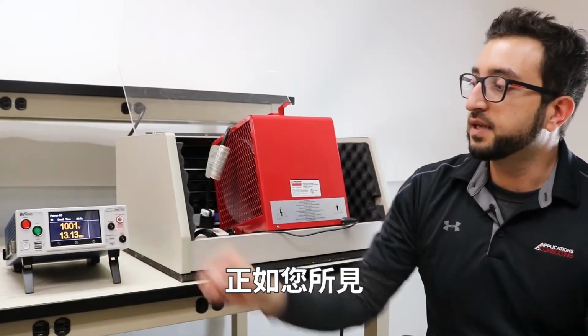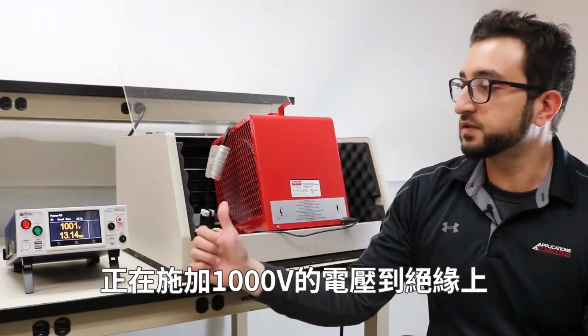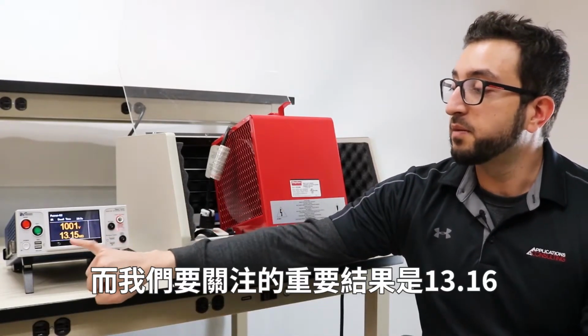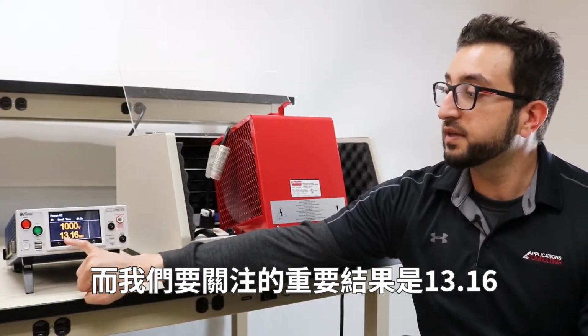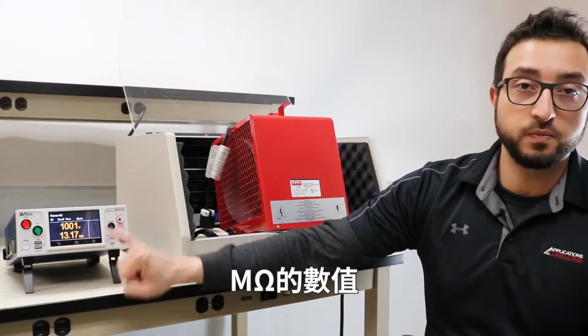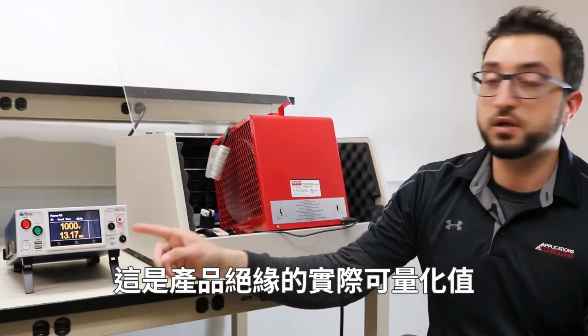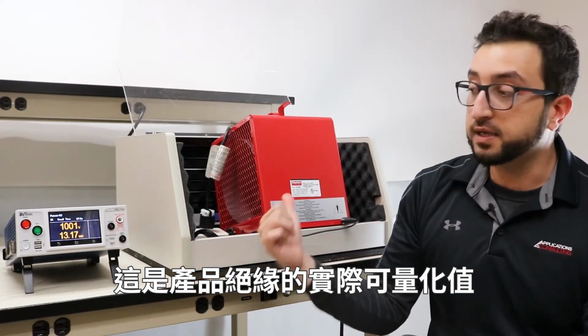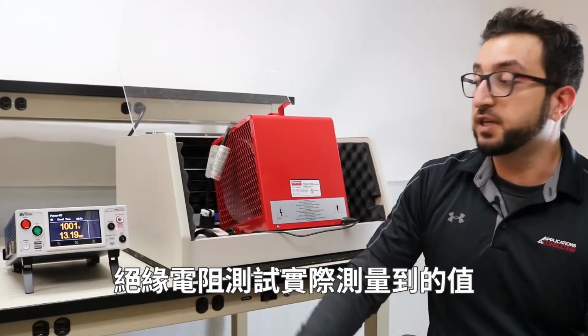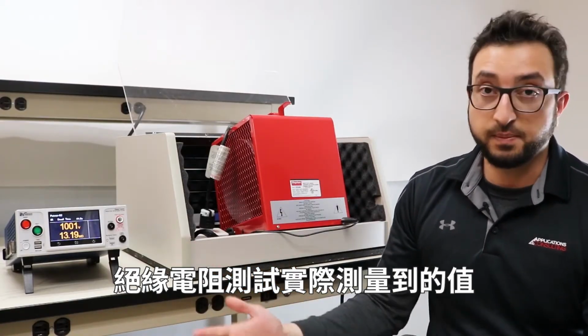And as you can see, 1000 volts is being applied across the insulation. And the important result that we're going to look at is the 13.16 mega ohm number. That's the actual quantifiable value of the product's insulation, which the insulation resistance test actually measures.